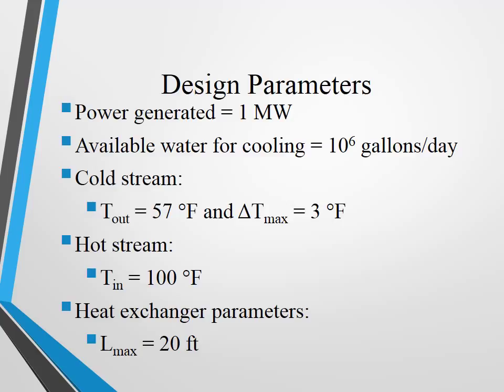The HPC outputs around 1 megawatt of power which needs to be dissipated. The available cooling water flows from a reservoir at 57 degrees Fahrenheit at a rate of 1 million gallons per day and should not exceed 60 degrees Fahrenheit when leaving the exchanger. The hot stream from the computers is assumed to be leaving with a maximum temperature of 100 degrees Fahrenheit. Lastly, the heat exchanger should be 20 feet or less in length.